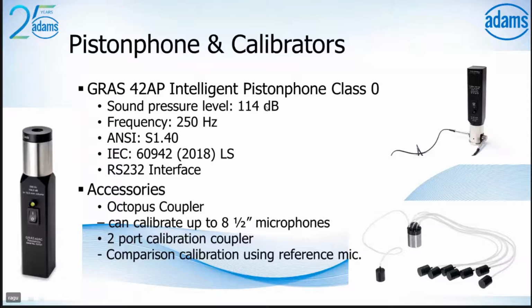GRAS gives you accessories that can be used along with the piston phones. So here we have a dual port coupler that can be used along with the 42AP, where you can use a master reference microphone, a microphone that is calibrated and kept as a master microphone, for a level check using the 42AP. So you can introduce your DUT, the microphone that you will be using for your measurements. And then we have something called the octopus coupler.